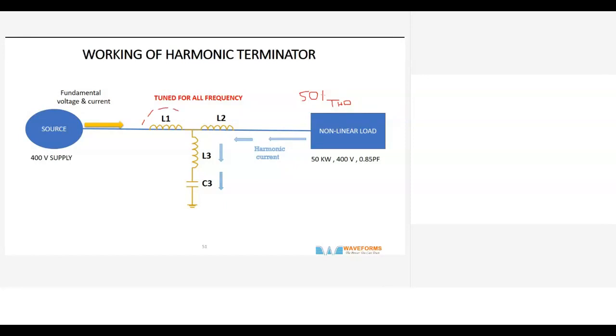filter anything. It will pass anything below the fifth harmonic, but it will try to stop the harmonics at the 5th and above. So the residual harmonics circulate here in small quantities. Okay, we use a tuned circuit. So this capacitor and this inductor LC are tuned. You create a low impedance path by designing the inductor and capacitor in such a way that XL is equal to XC, and so the impedance is almost 0. So the harmonic currents tend to flow through this and to the ground. So you have a complete filtering.